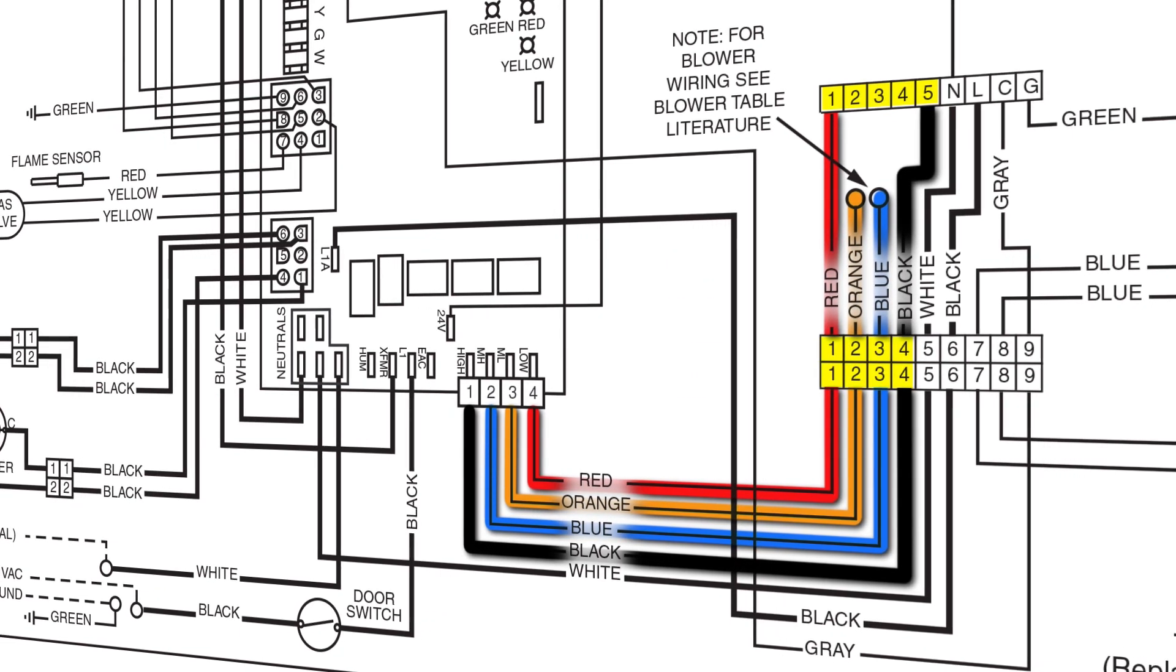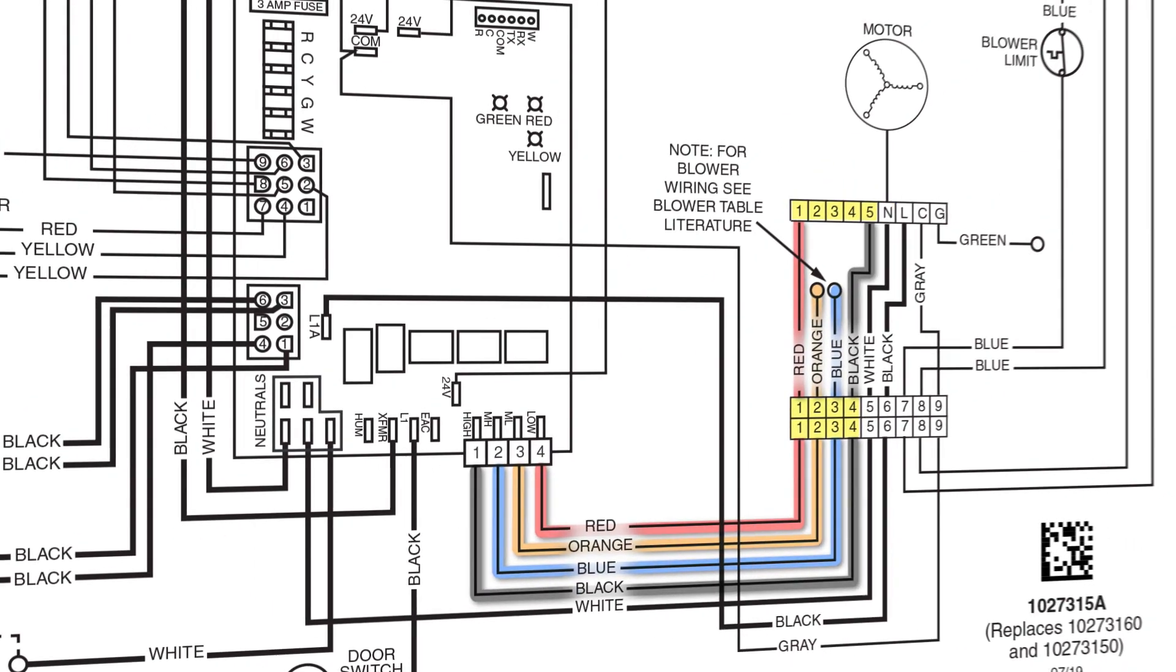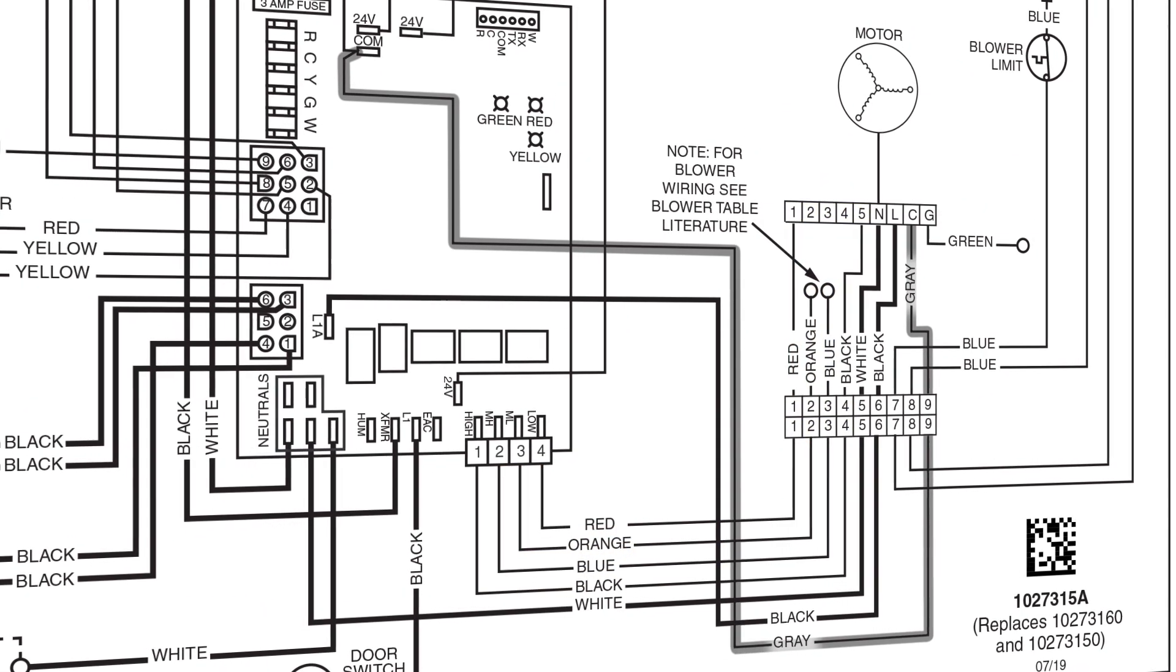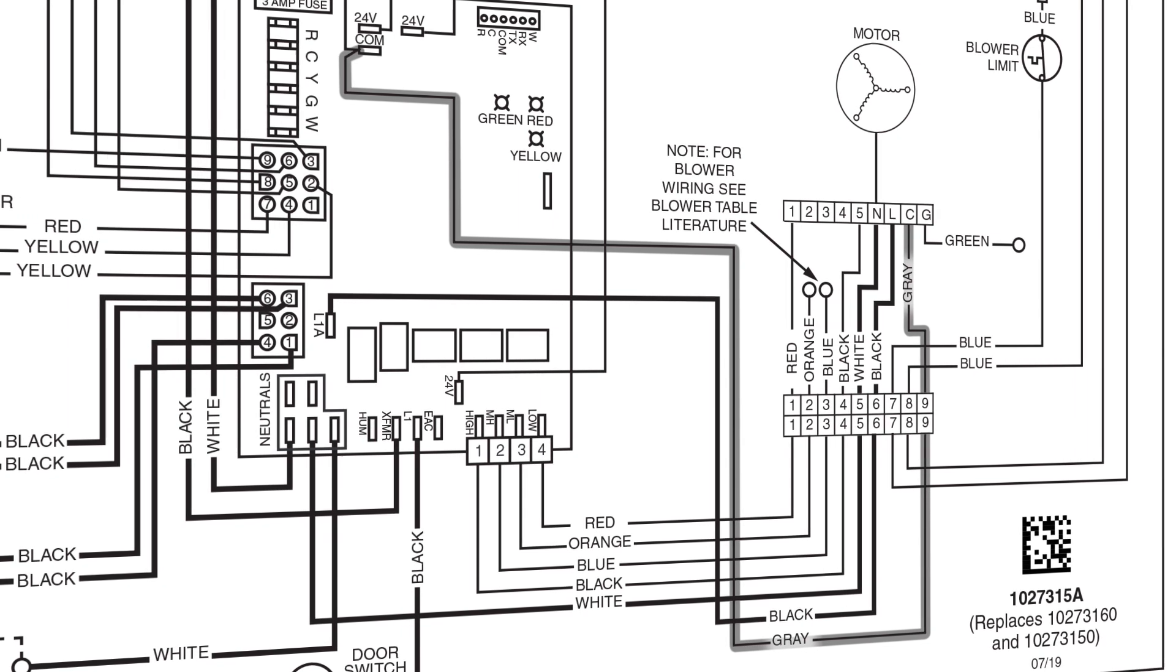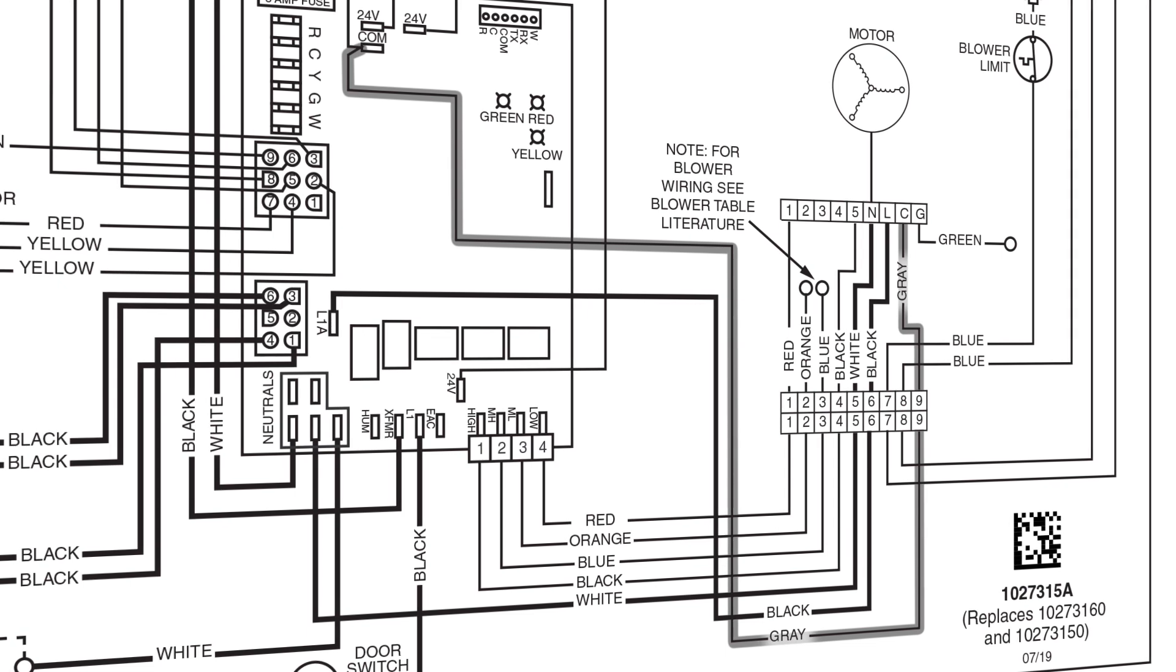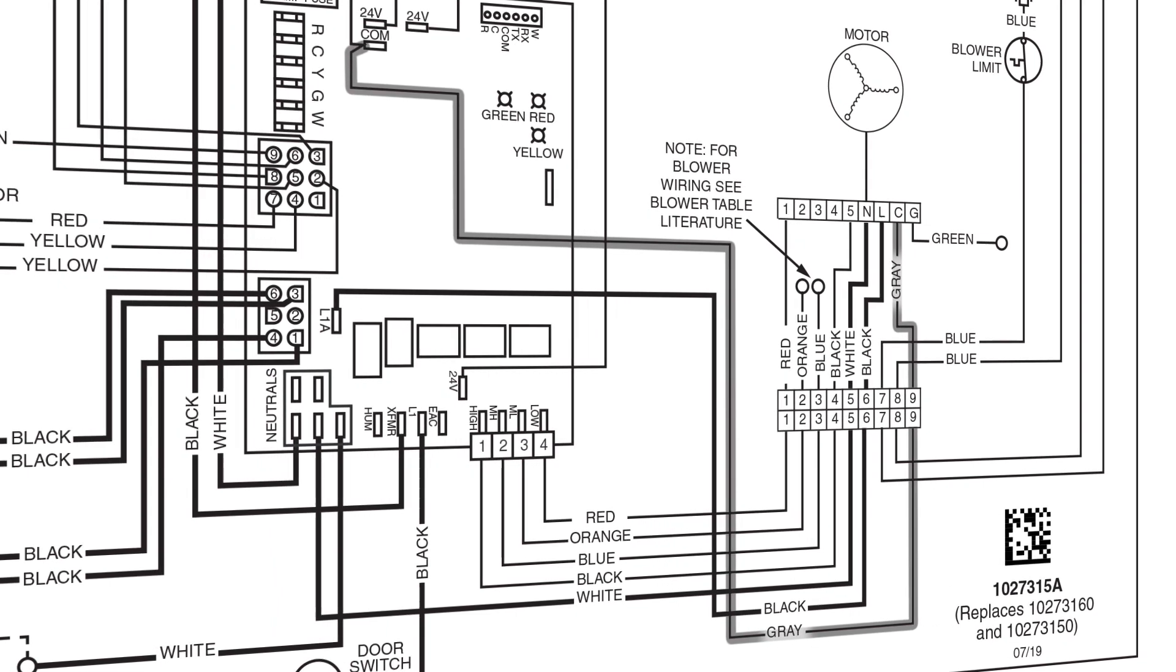Also what we'll have is a gray wire that will be a 24 volt common, which we need that in order to get 24 volts to the motor. So again, you'll have line voltage and you'll also have 24 volt VAC voltage going to the motor.